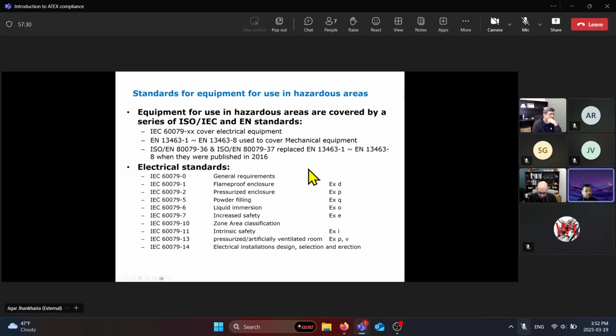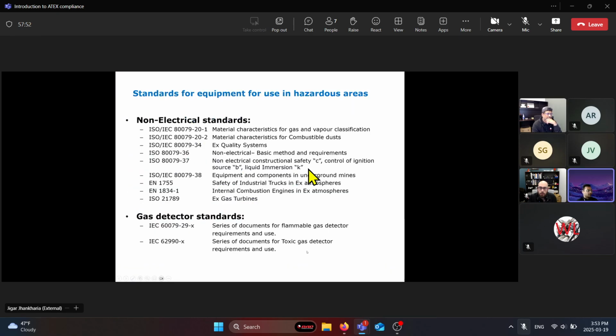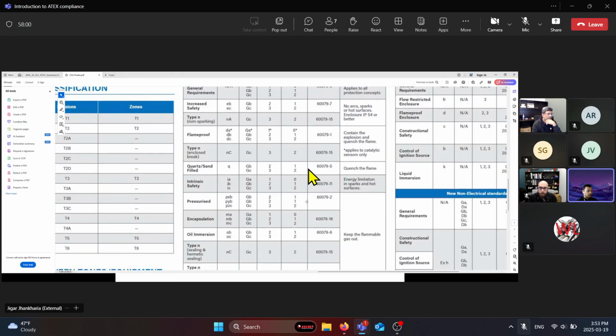Dash 13, pressurized artificial ventilated room. This is usually for any large ventilated areas where they are processing chemicals or something like that. Basically, it requires an area classification first, and then do the evaluation against that standard. Dash 14 is just for electrical installations, design, selection, and erection. Like I mentioned, there are non-electrical standards, but before we move into that, I'll quickly go over the zone 20, 21, 22 requirements.